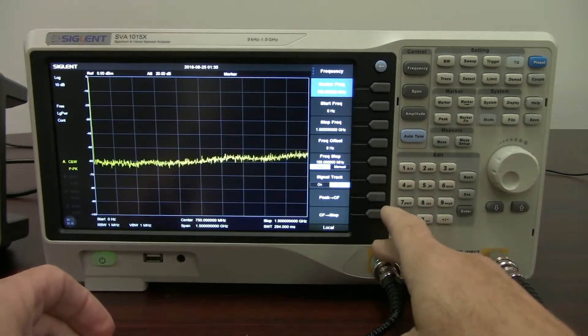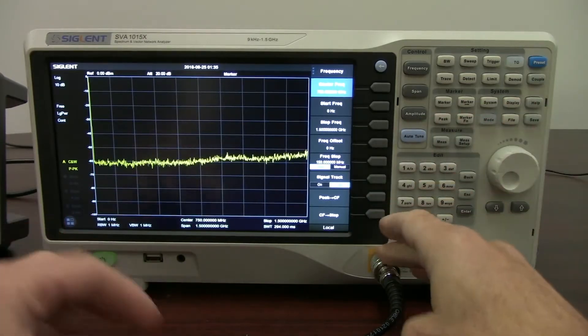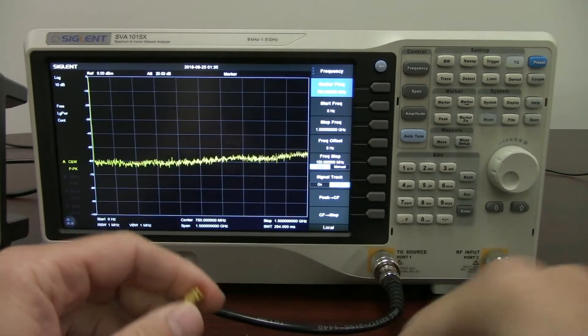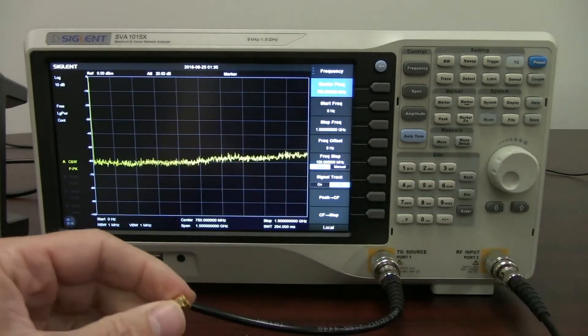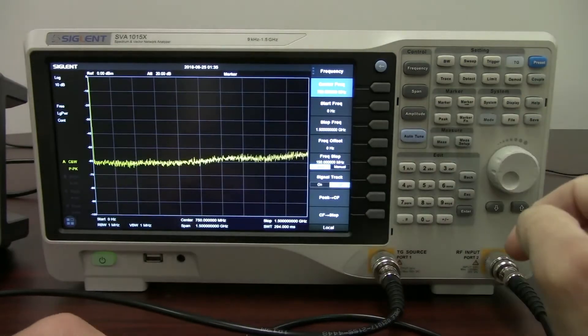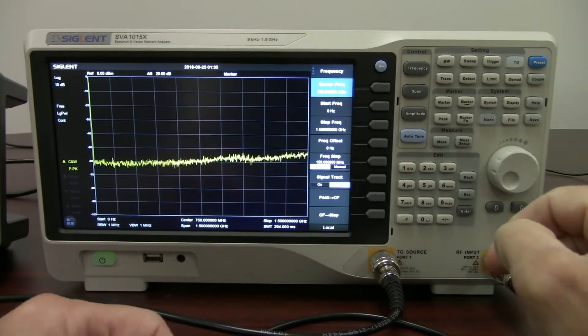So the tracking generator signal is going to be output through this port, through this cable, and then it's going to go through our attenuator. We're going to then measure it with this port, the RF port, and we're going to look at the output on the front panel of the display here.